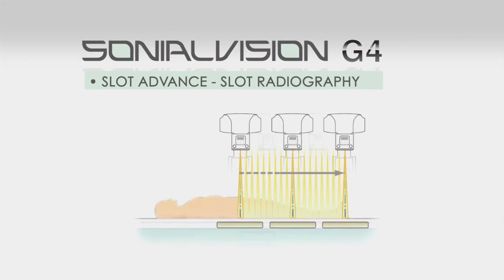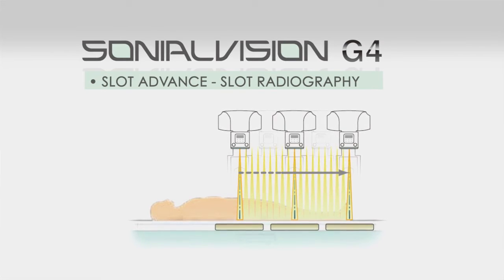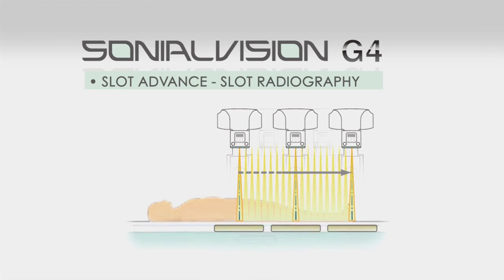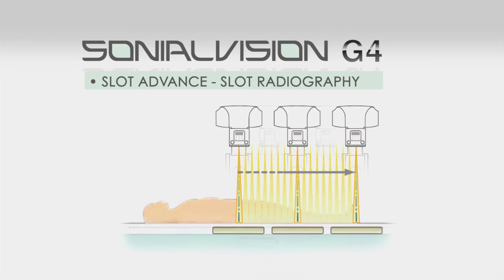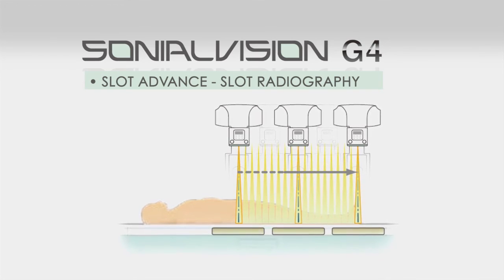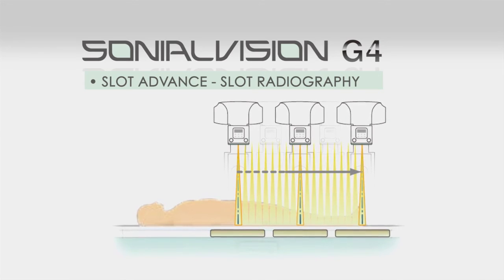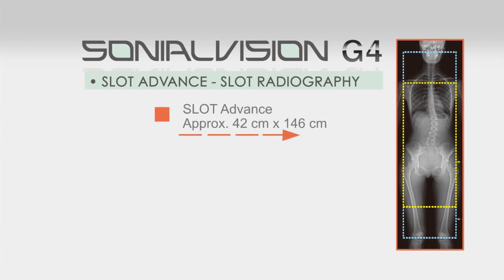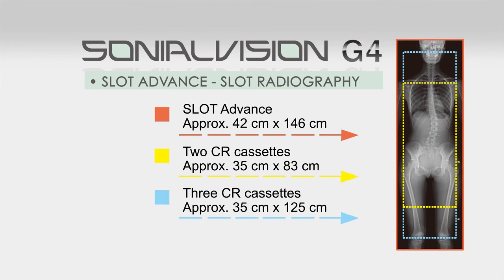Slot Advance, Shimadzu's slot radiography application, collimates the X-ray beam so that it only exposes a narrow central slit field without distortion caused by oblique rays. These central slit images are captured using the SonialVision's super high-resolution flat panel detector by moving it in parallel with the X-ray tube. These successive images are then automatically reconstructed to create one long image in SonialVision G4's digital imaging unit, enabling very high accuracy measurements without distortion, even with a very simple workflow.